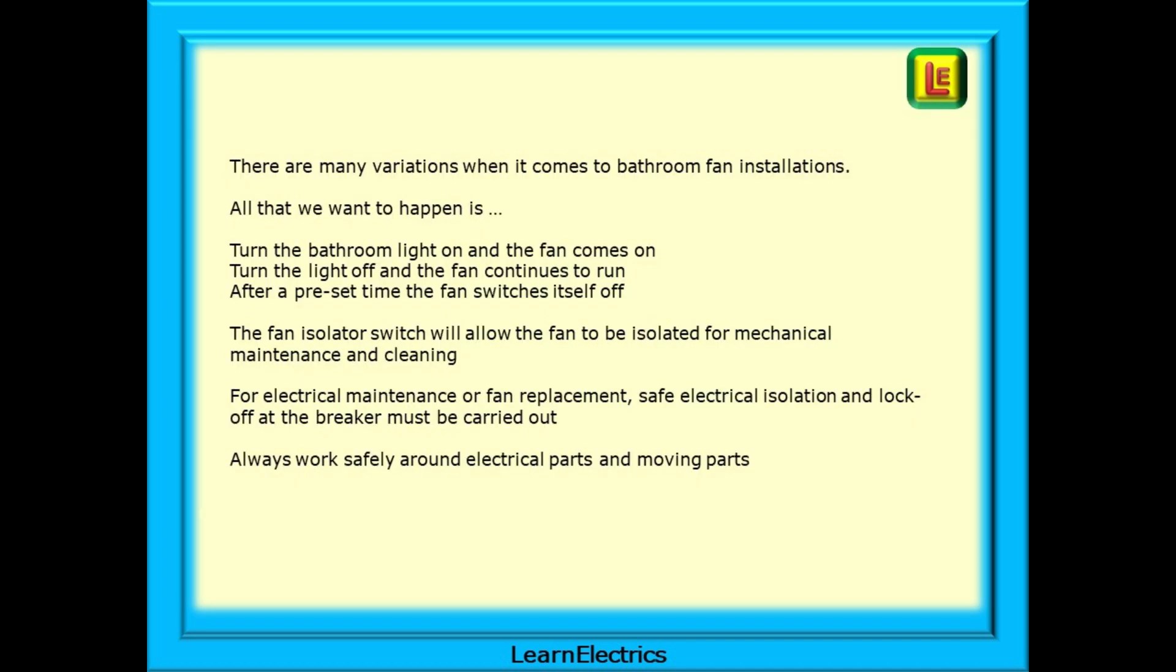There are many variations when it comes to bathroom fan installations. All that we want to happen is that when we turn the bathroom light on the fan comes on. When we turn the light off the fan will continue to run until after a preset time the fan switches itself off. For safety the fan isolator switch will allow the fan to be isolated for mechanical maintenance and cleaning. But for electrical maintenance or fan replacement safe electrical isolation and lock off at the breaker should be carried out so that no one can accidentally energize the circuit. Always remember to work safely around electrical parts and moving parts.